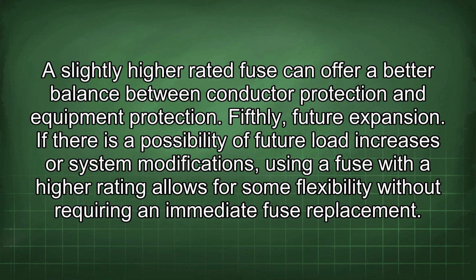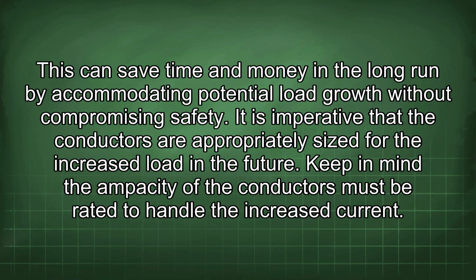Fifthly, future expansion. If there is a possibility of future load increases or system modifications, using a fuse with a higher rating allows for some flexibility without requiring an immediate fuse replacement. This can save time and money in the long run by accommodating potential load growth without compromising safety. It is imperative that the conductors are appropriately sized for the increased load in the future. Keep in mind the ampacity of the conductors must be rated to handle the increased current.